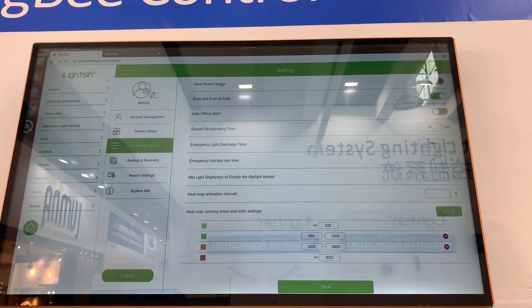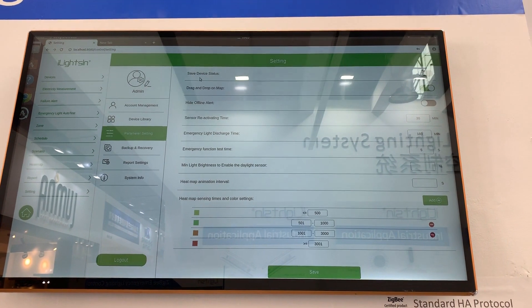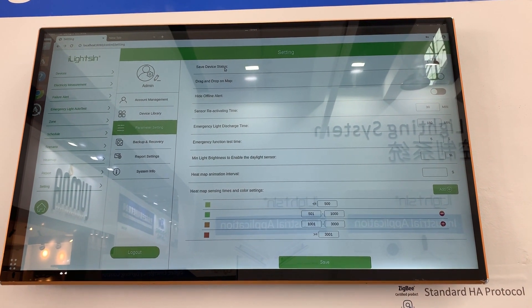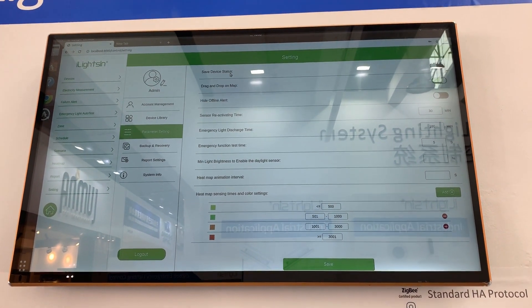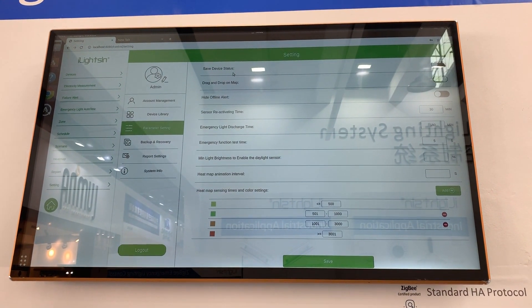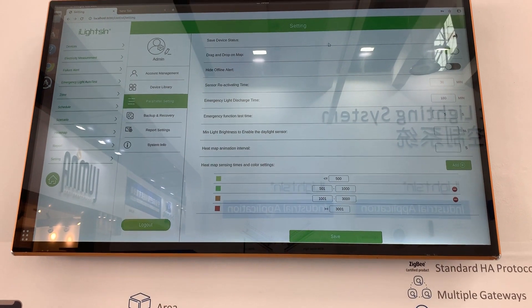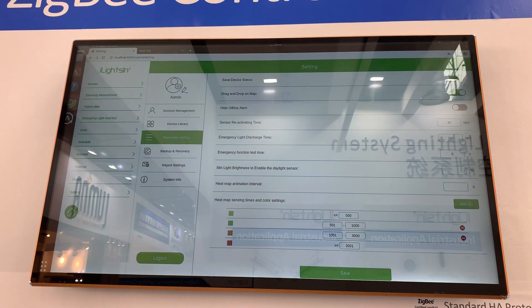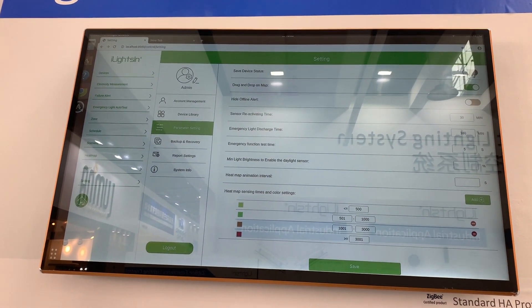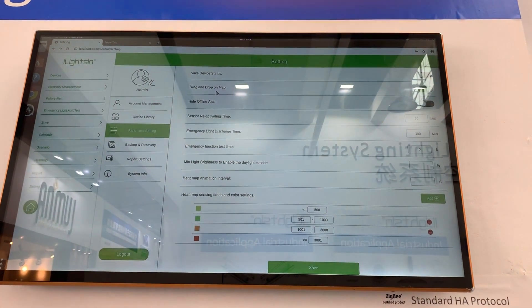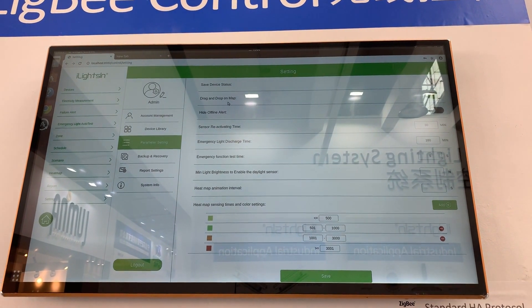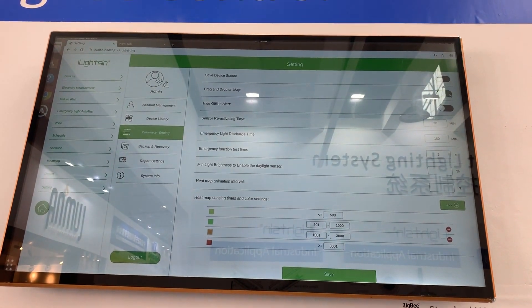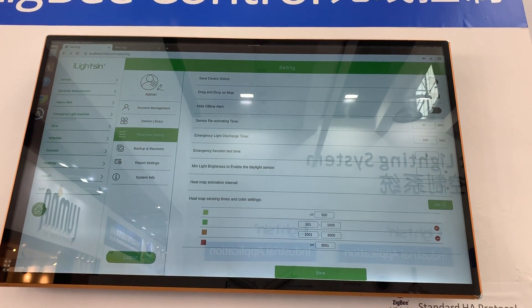Parameter settings. There are many settings for detailed requirements. Save device status is to save the device status after power off. For example, if it's currently at 50% brightness and you power it off and on again, if you want it to return to 50%, you need to enable this option. If not, the device will go to 100% brightness when powered back on. Drag and drop map — when programming, you drag and drop everything on the map, but after everything is done, it's better to close this so people won't accidentally change settings.